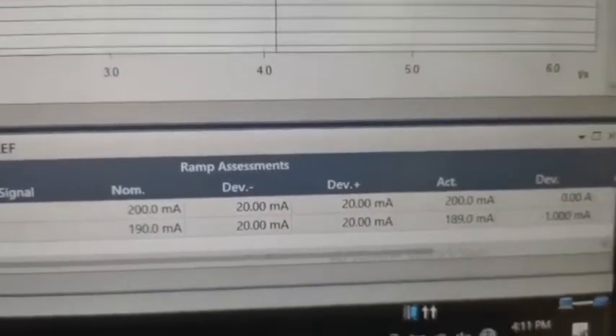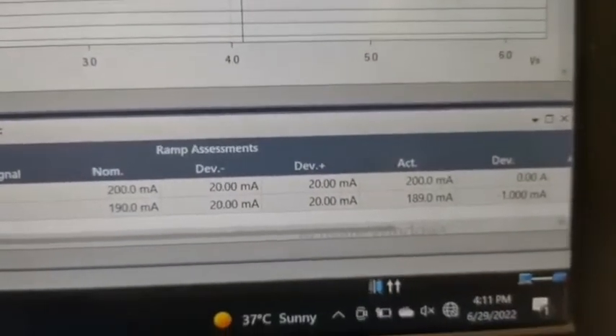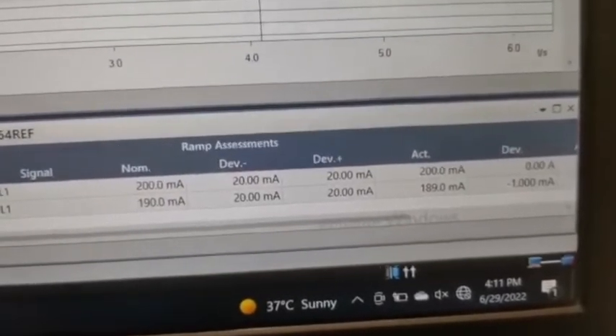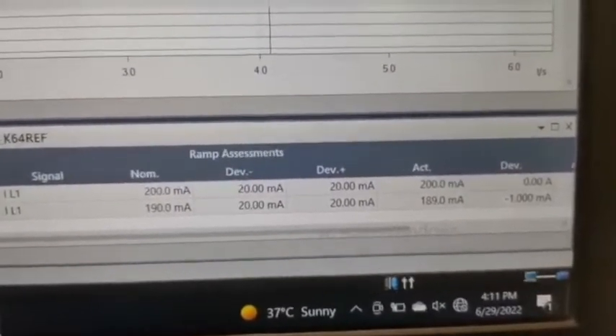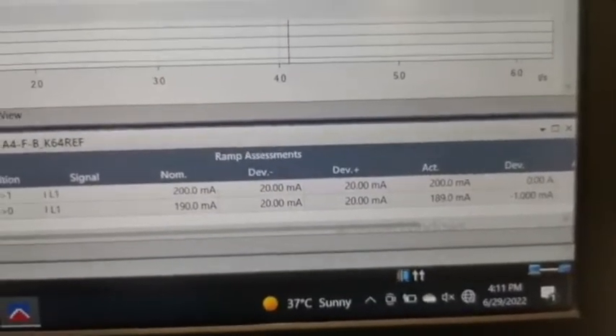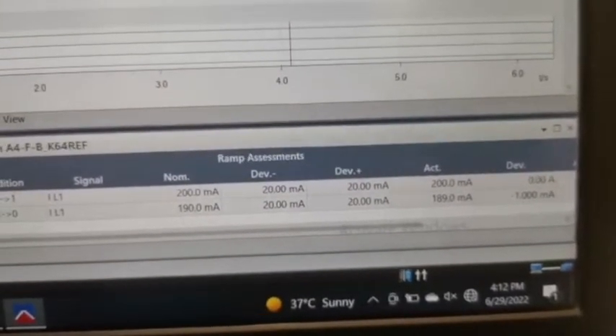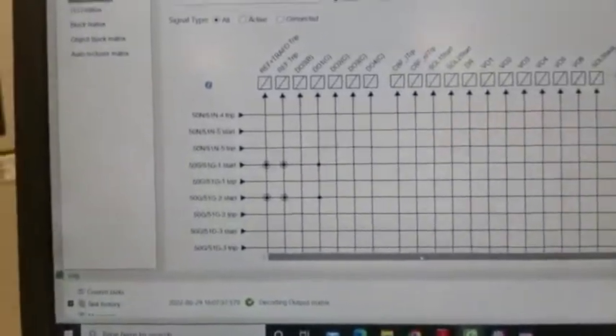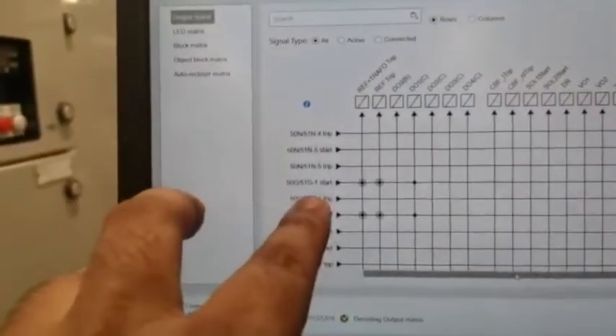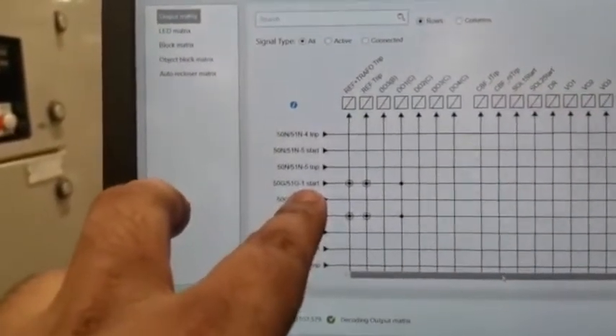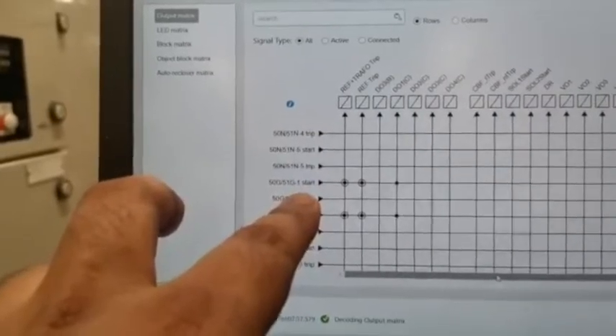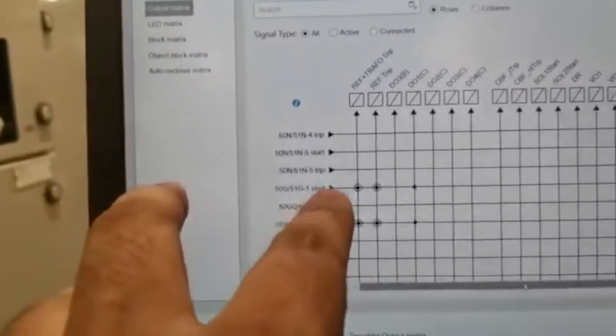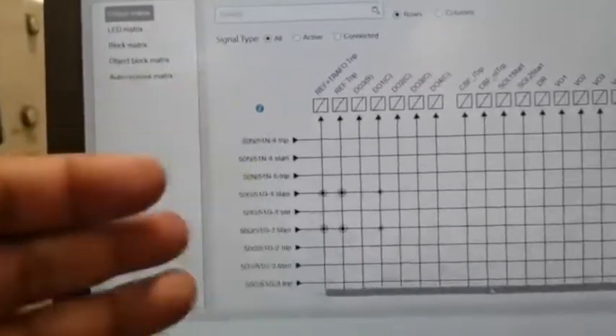The actual pickup is exactly 200 milliamps and the dropout is 189 milliamps. This is our pickup and dropout result for the REF function. For the trip test, we are using the same start contact because the protection is instantaneous with no time delay, so we are taking the start contact directly as the trip contact.